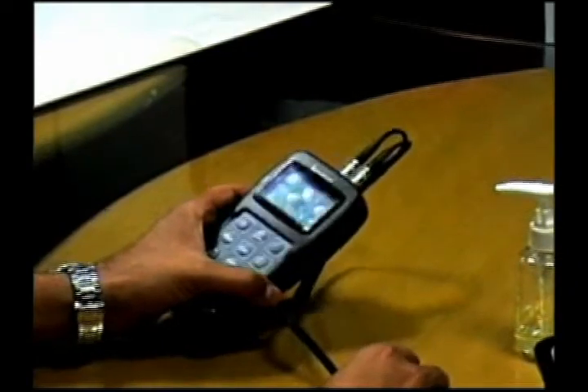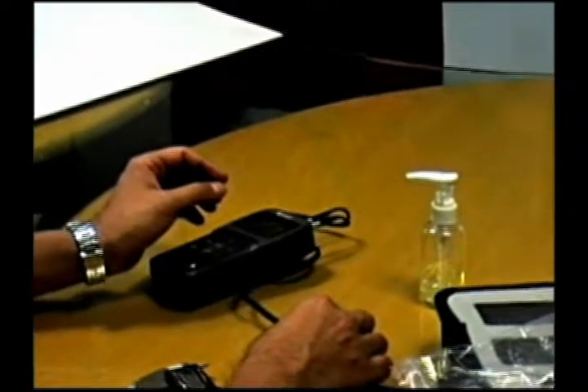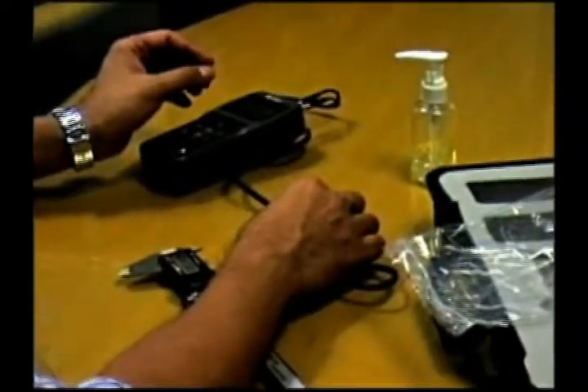There are two ways the instrument is utilized: either by having a known thickness measurement of the material that we are going to test to calibrate the instrument, or we know the material velocity.